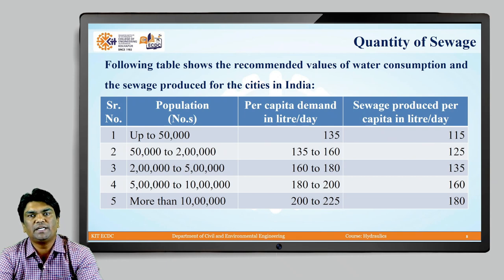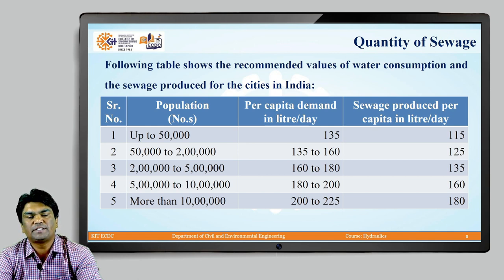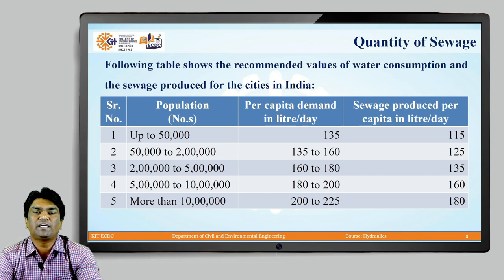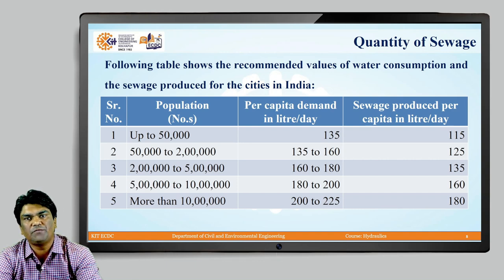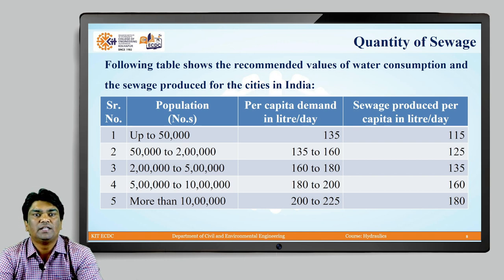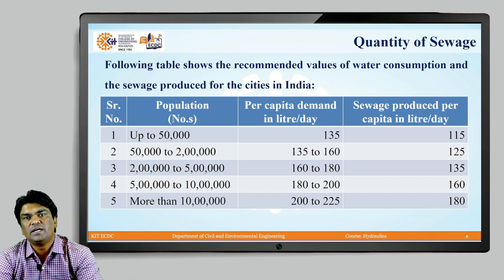This table shows the recommended values of water consumption and sewage produced for cities in India, presenting per capita demand in liters per day and sewage produced per capita per day. For example, if the population is up to 50,000, the per capita demand is assumed to be 135 liters per capita per day, and sewage produced is around 115 liters per capita per day — approximately 70 to 80 percent of supply. Multiplying 115 by the population gives the average daily sewage flow.